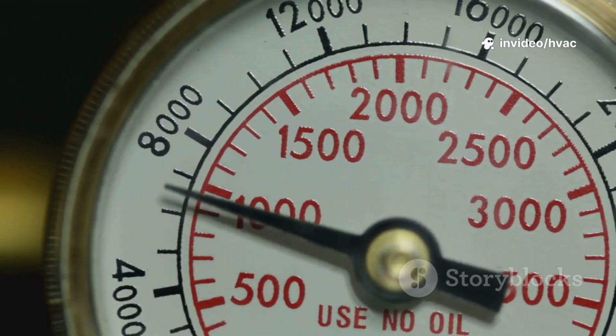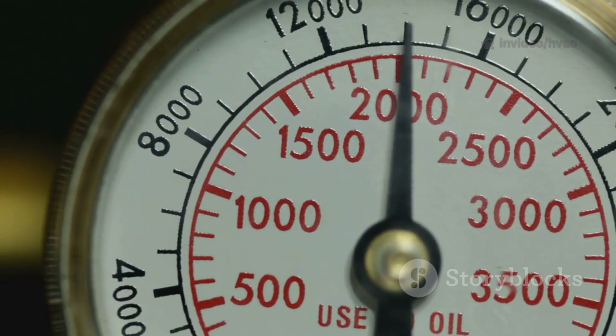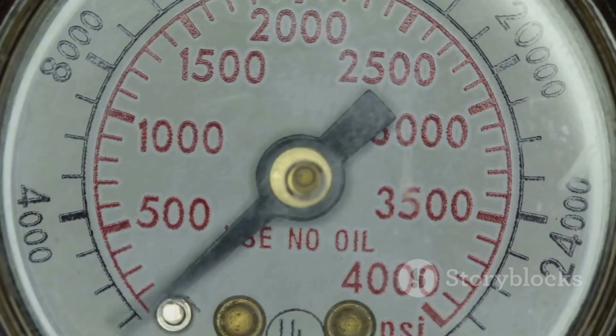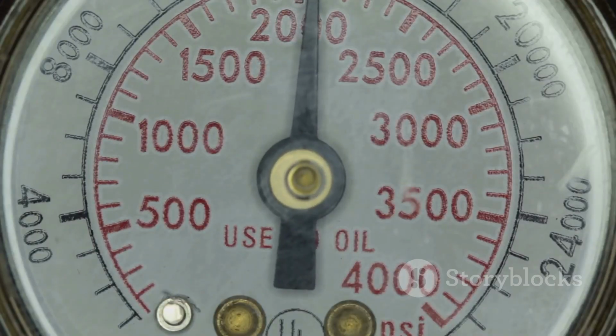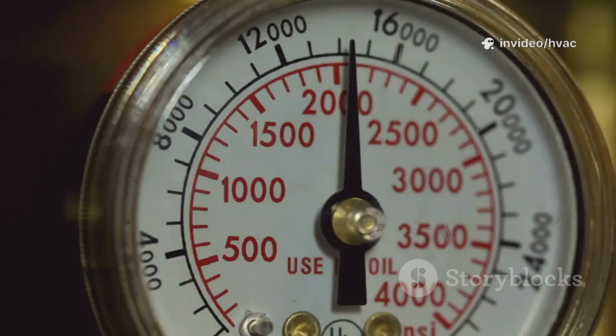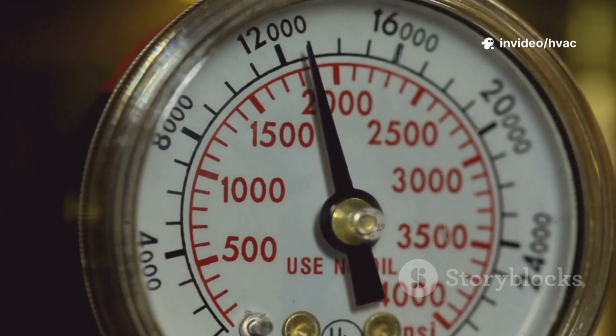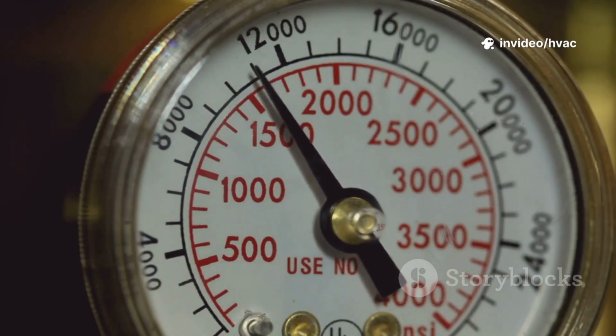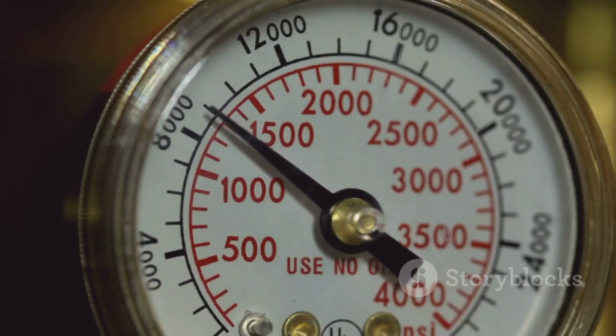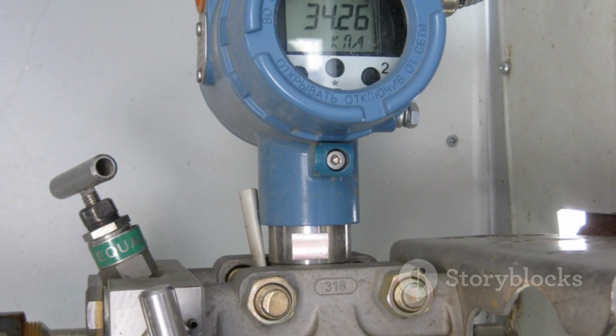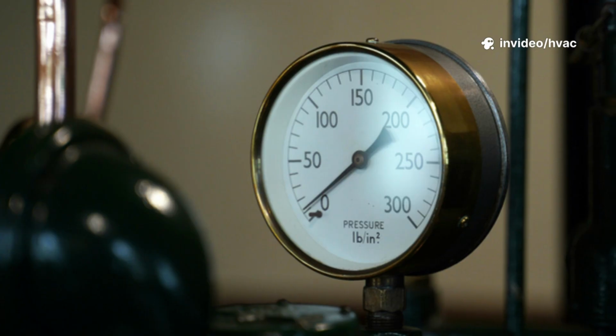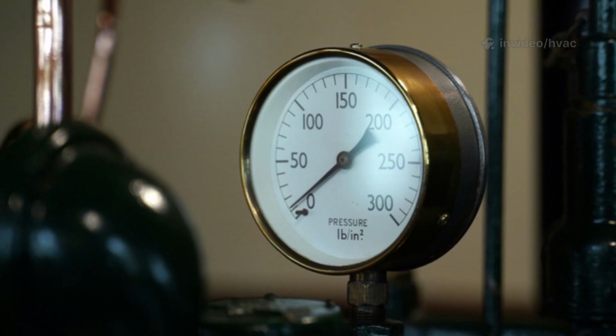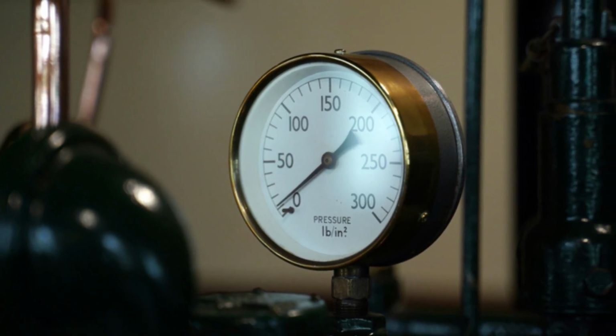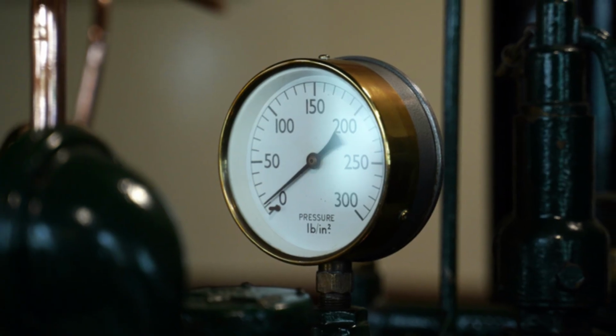After you've found a valve with the correct flow rate range, you also need to check its required operating differential pressure. The manufacturer's datasheet will specify the minimum and maximum pressure drop the valve needs to function. For example, the 3/4 inch valve we found might require a minimum of 5 psi to operate and have a maximum rating of 60 psi. Our system's pressure range is 10 to 35 psi. Since this range is entirely within the valve's acceptable limits of 5 to 60 psi, this valve is an excellent choice. But if our system pressure could drop to, say, 3 psi, this valve wouldn't work correctly and we'd need to find a different model with a lower minimum pressure requirement.